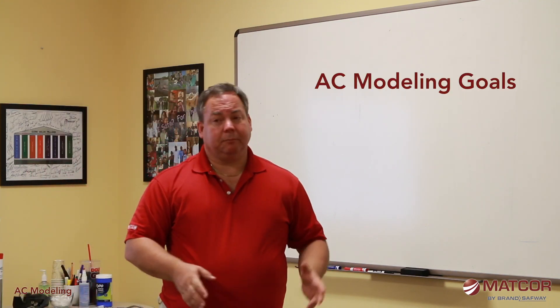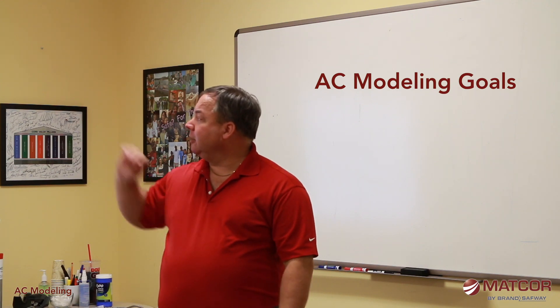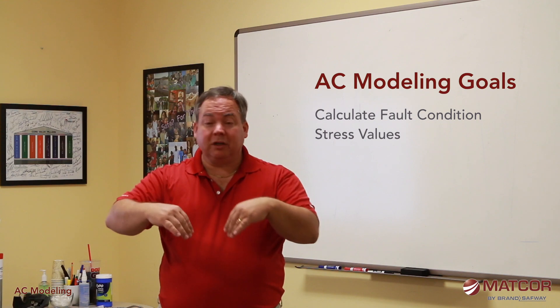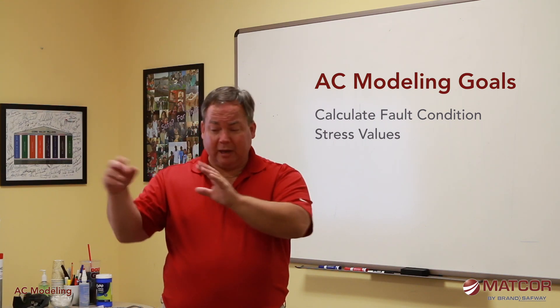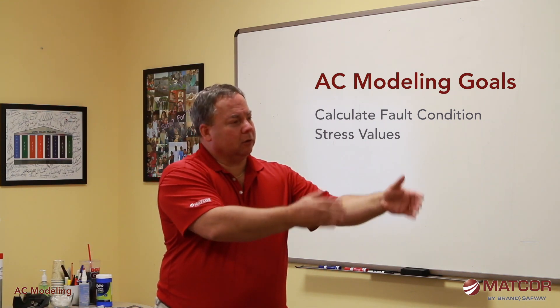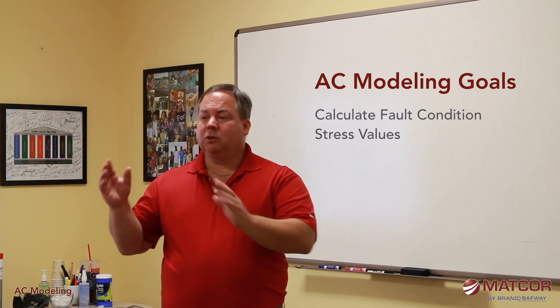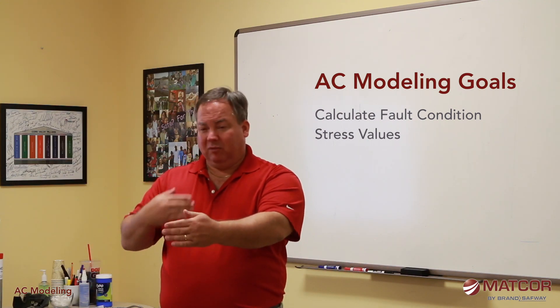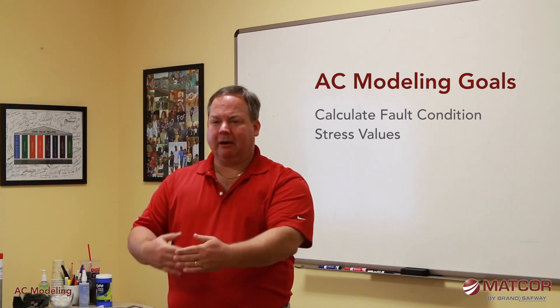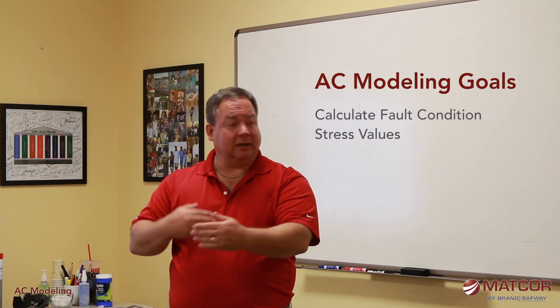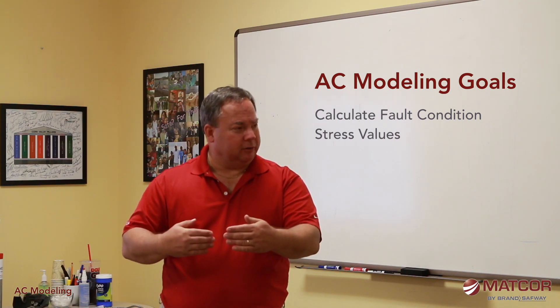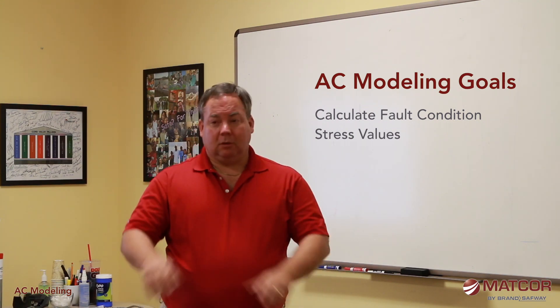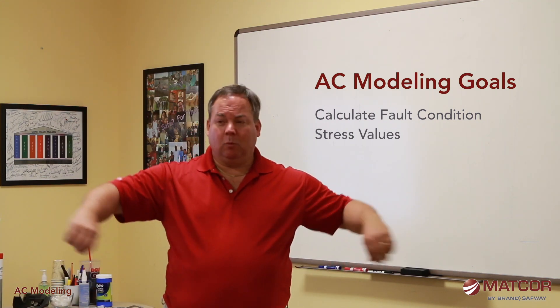The goals when you do AC modeling are straightforward: we want to calculate fault condition stress values. During a fault condition, we look at the worst-case fault at each individual tower and how that affects the pipeline — given the pipeline's relationship to that tower, how far away it is, how deep it is, and what the resistance is at that location. We literally model every tower along the length of the co-location.